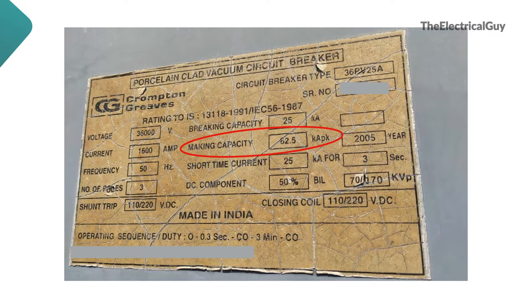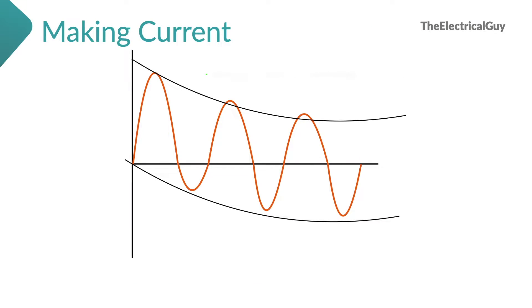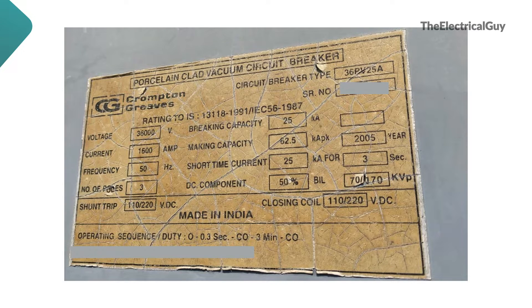Next is making capacity. If the breaker closes during an existing fault condition, current may increase to a very high value during the first cycle, remaining in the system for a very short time. Therefore, the breaker must withstand this high current and the mechanical forces caused by it. This current is called short-circuit making current or rated peak withstand current. It is generally 2.5 times the rated short-circuit current at 50 Hz. So multiplying 2.5 with 25 kA gives us 62.5 kA as the making current.